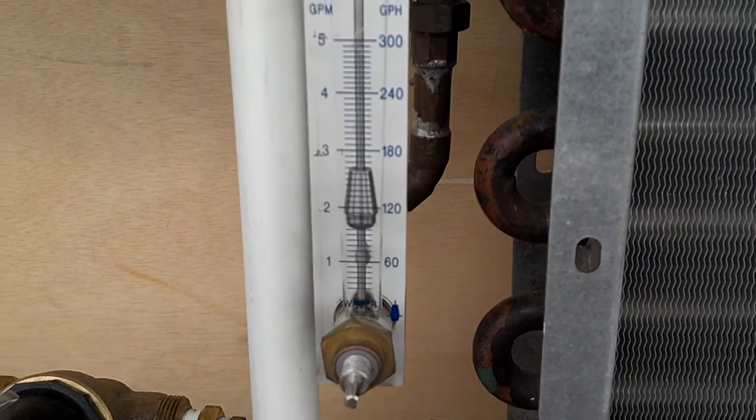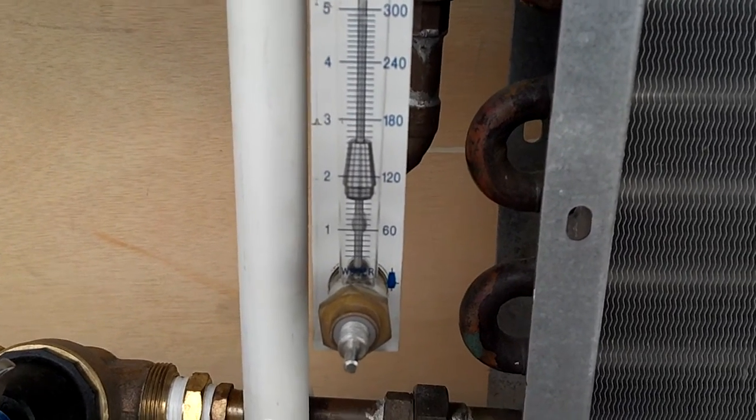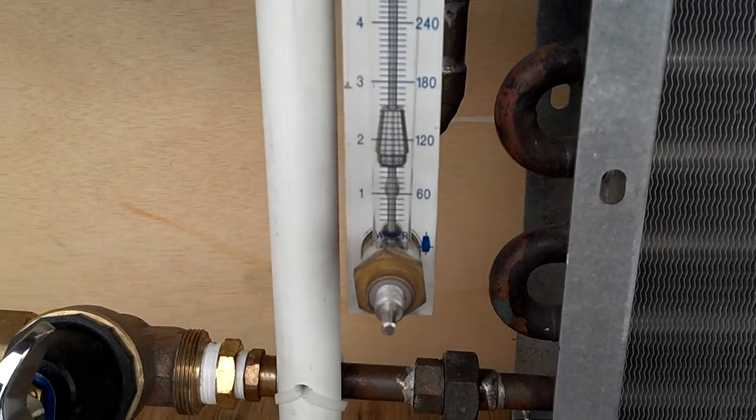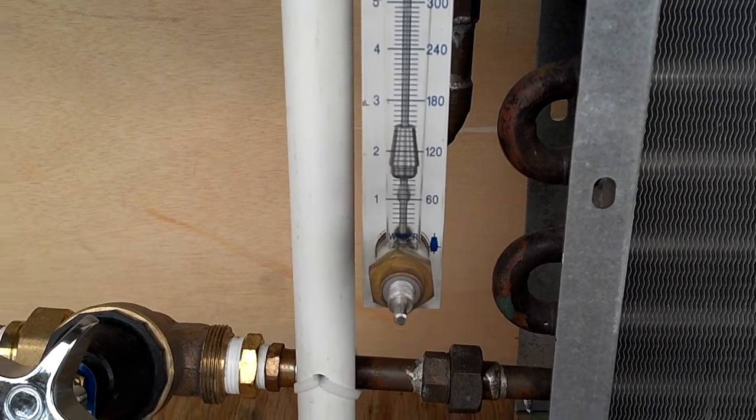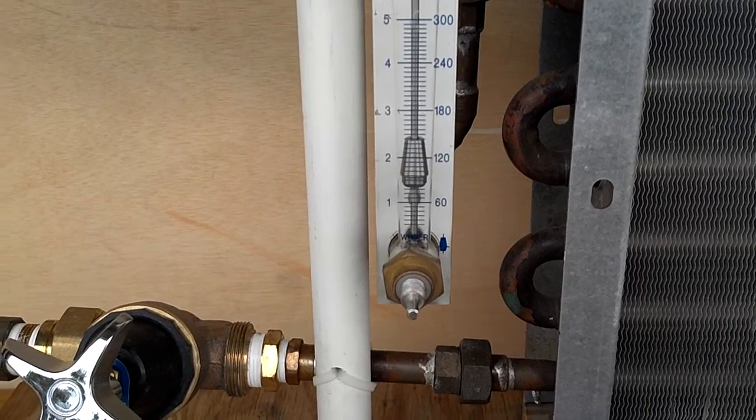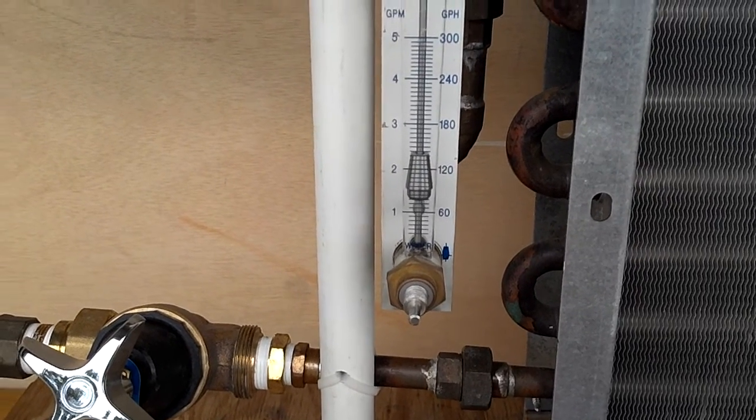The valve is still closing and you can see it's doing its job. I'm going to stop it at about a gallon a minute. Right now what we're simulating is on a hot day, the chilled water system is running.